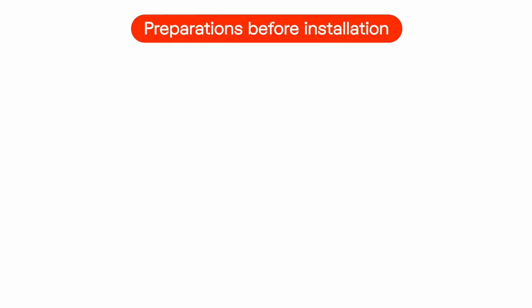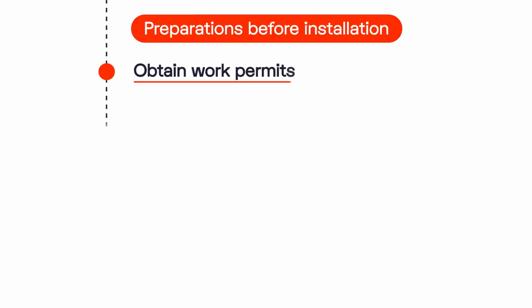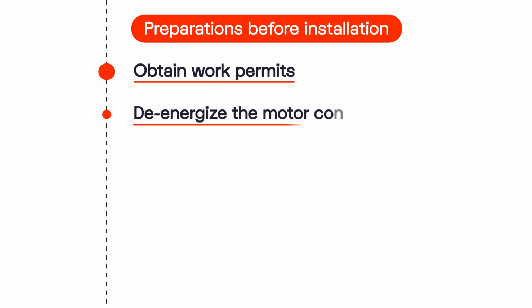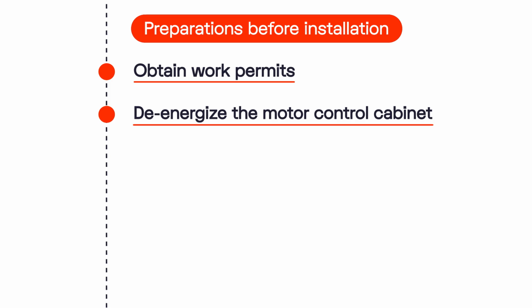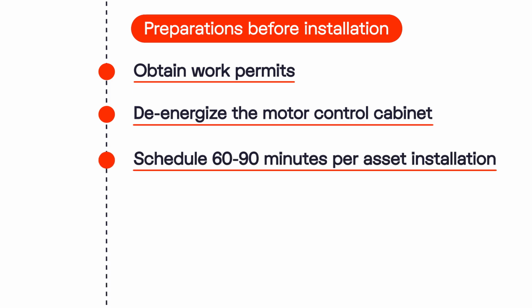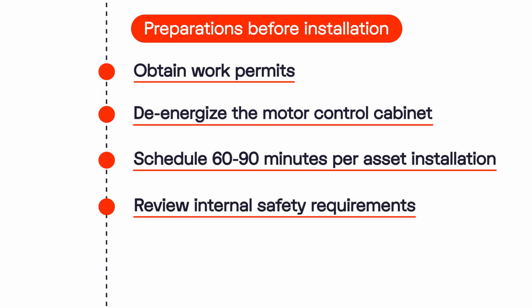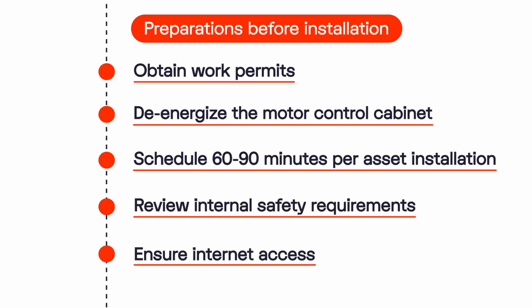Before you start installing, please prepare the following success factors. First, ensure that any necessary permits have been approved prior to the intended installation date. Second, make sure that the motor control cabinet can be de-energized during installation. Third, plan sufficient time. Installation should take 60 to 90 minutes per asset. Make sure to add in a buffer for unforeseen circumstances. Fourth, review your organization's internal safety requirements regarding circuit protection and proper fusing. And last, ensure the ongoing availability of a network connection or sufficient mobile signal strength.